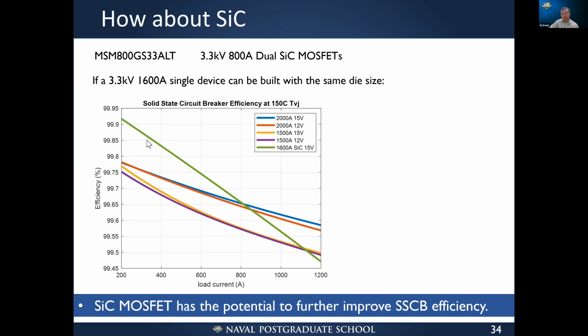So then we compare that. This is a green curve. Compare that with the 2000 amps and 1500 amps IGBT. You can clearly see the benefit; this is with 15 volt gate voltage, right? So efficiency is much higher at light load for sure, as we expected. And efficiency is comparable at the heavy current, okay?